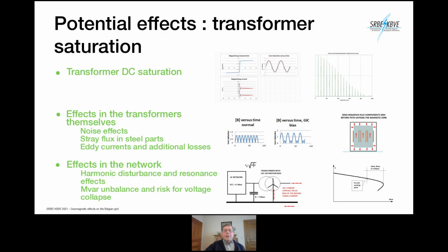Another effect is the sharp increase of the 50 hertz component of the magnetizing current. And this means an additional megavar load on the generators in the grid. And this is not a problem as long as the pre-GIC situation is such that you are in a stable part of the voltage versus reactive power characteristic you see at the bottom right. But as soon as you approach the nose of the curve, this may simply put your network in collapse, which means total blackout, and not for COVID reasons.